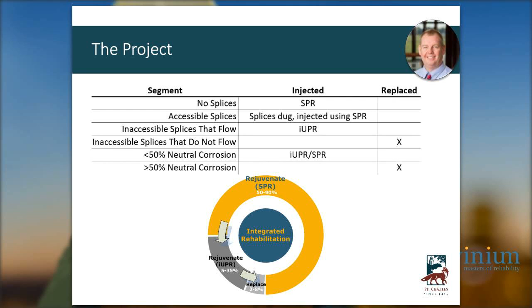It goes without saying, if you can't get at the splices or you can't flow the fluid, then you end up just having to send in the directional boring crews. One of the things that a lot of people don't take into account, but we have, is that as part of the Novinium testing on each cable before we inject it, if the neutral is more than 50% corroded, we have determined that we do not want to save that cable. We're going to go ahead and replace it, put new jacketed cable and pipe, and not inject a cable where the concentric neutral is more than 50% degraded.